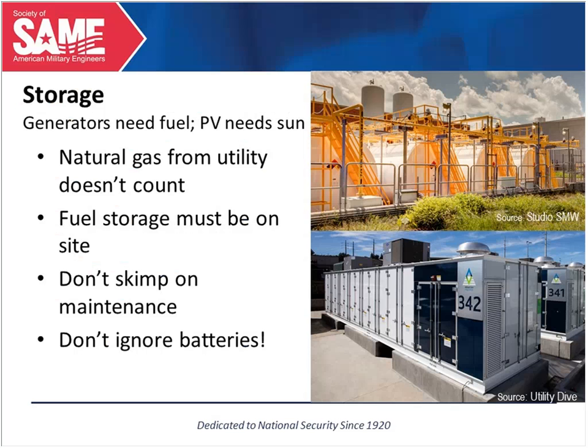A couple really important points. First, natural gas doesn't typically count as storage if it's coming from a utility off-site. Now, you can store natural gas, and we've done it. You can compress natural gas on-site, but you need to protect those big storage vessels. Unless you're doing that, if you're relying on an outside utility for your natural gas, it may even be more reliable than grid electricity, since trees aren't falling on your pipes usually. It's still not considered secure, because if there's a major event, it's likely that you're going to lose that gas feed.